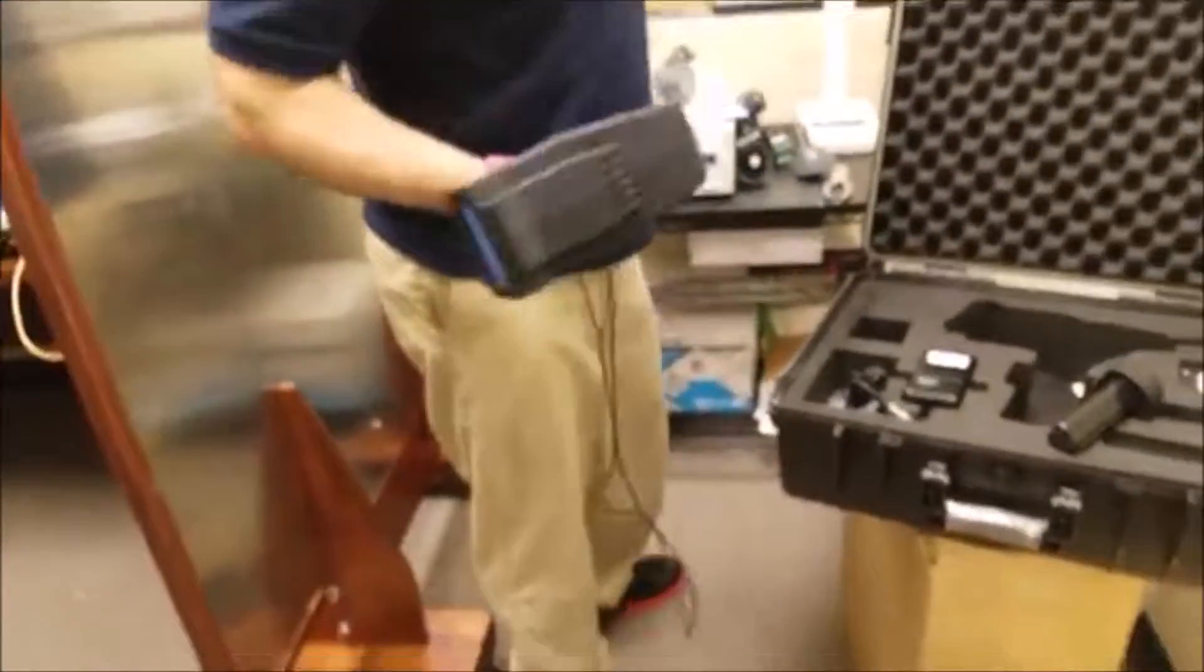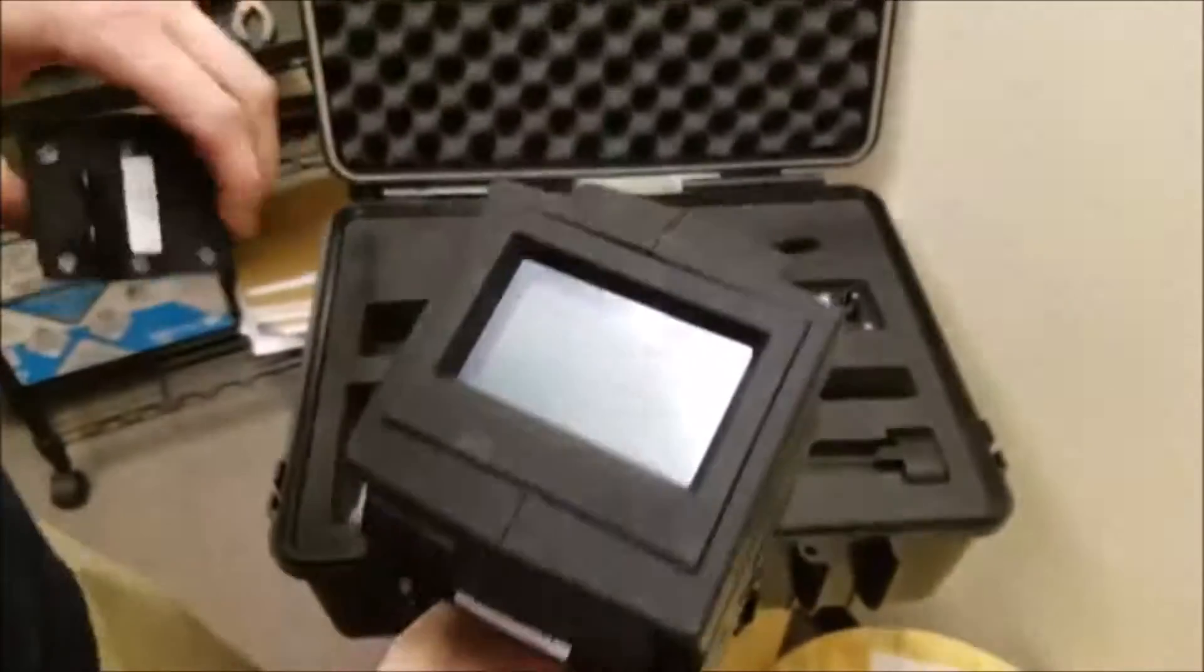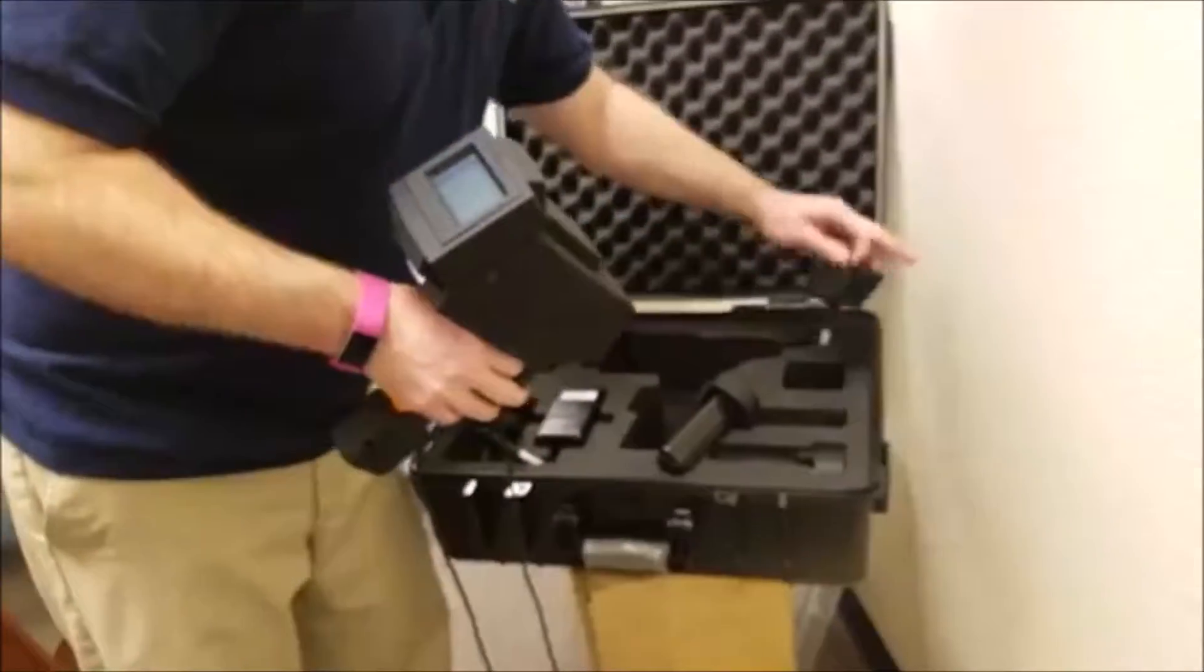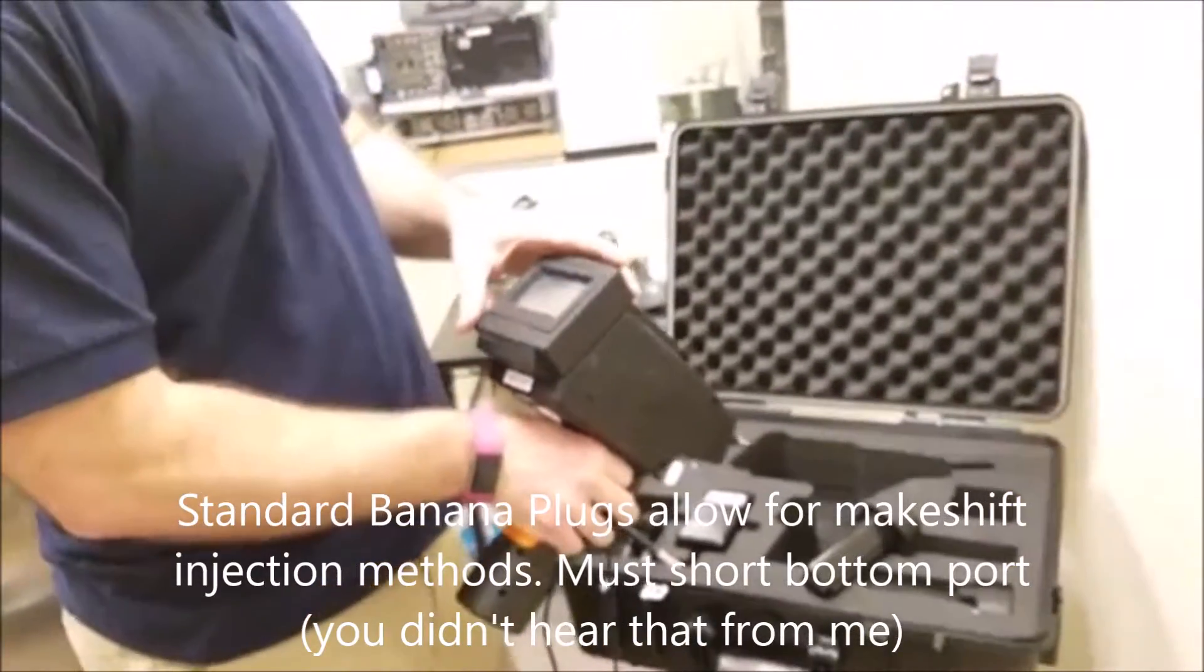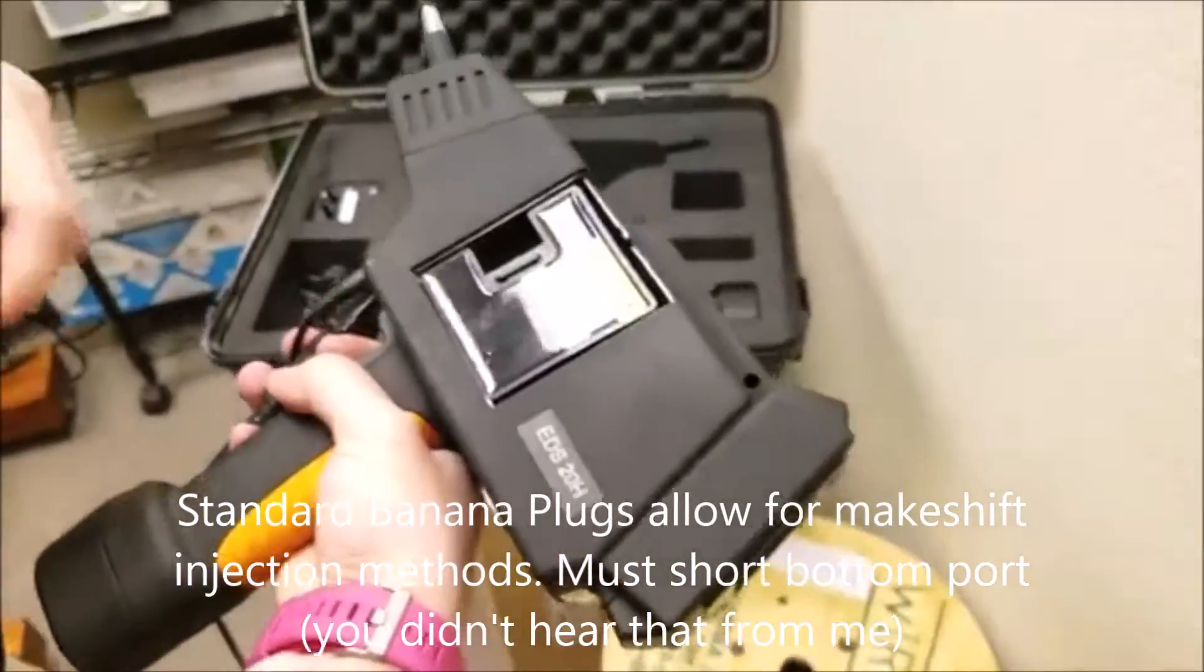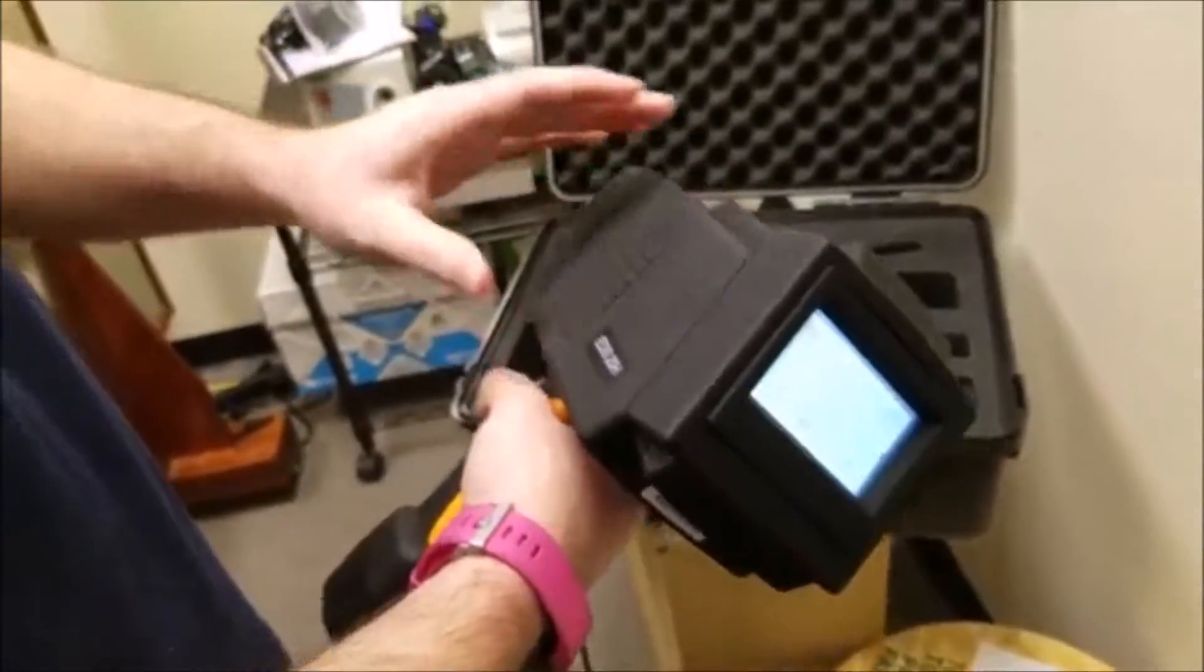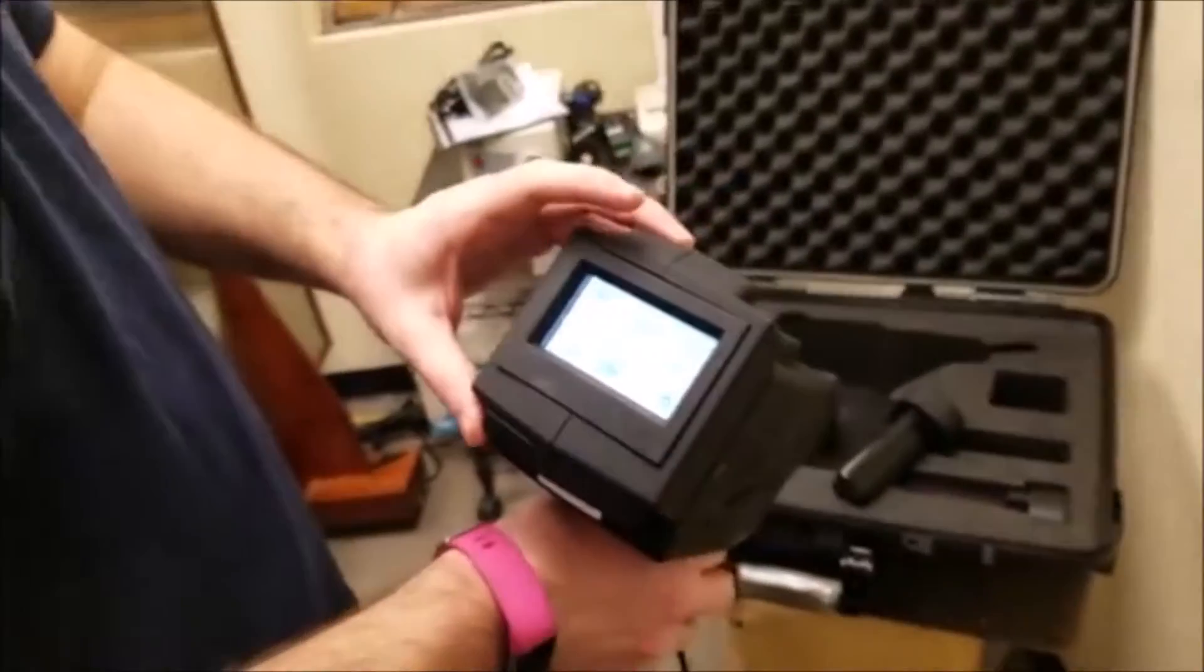Let's go back here really quick. We're going to do a quick air voltage run on it. I pulled the tip off while the unit was on. It didn't like it, it yelled at me and turned it off. So let me go ahead and stick the air tip on, turn this guy back on. And by the way, a discharge network is in there for easy removal and replacement. Standard discharge networks, like an HBM 100 picofarad 1500 ohms, would be available as well.